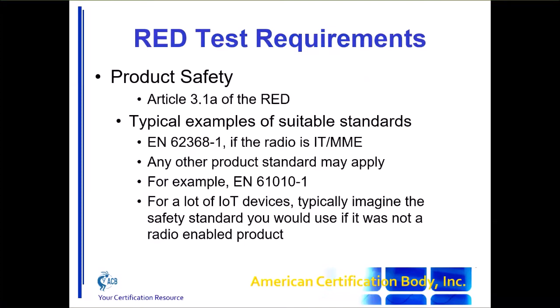Really, you've got to look at the whole product and say, well, what is my appropriate safety standard? So if you're making an ITE or multimedia equipment, then 62368 does make sense. But if, for example, you're making test and measurement equipment, then 61010-1 might make sense instead. So for a lot of these IoT devices, there might be a product safety standard that you wouldn't necessarily associate with radio, but you would still pick the correct product safety standard for your product.